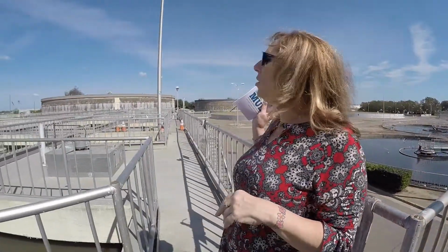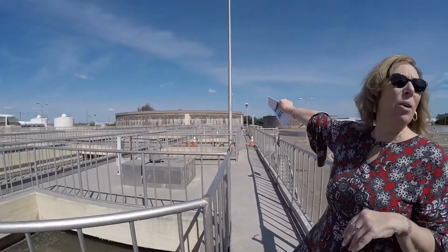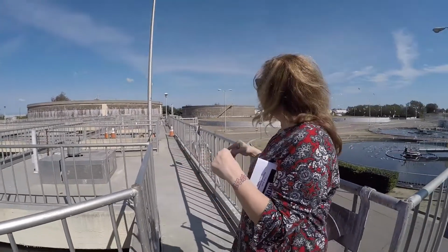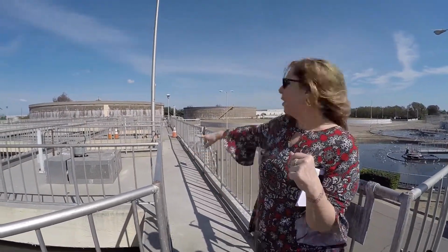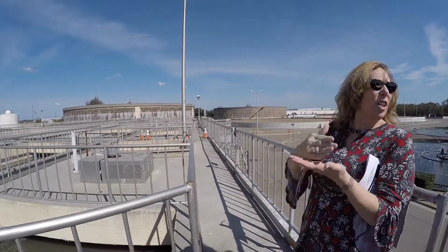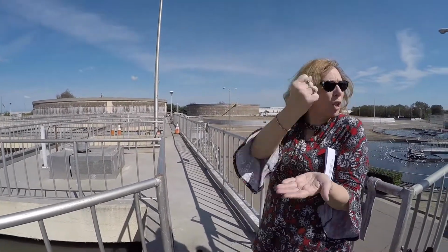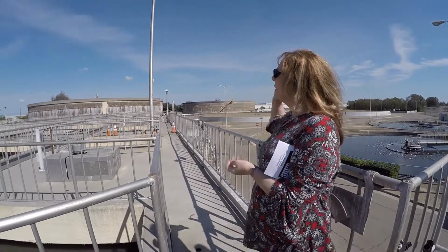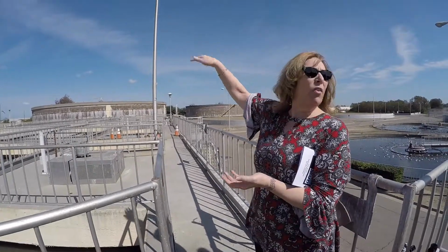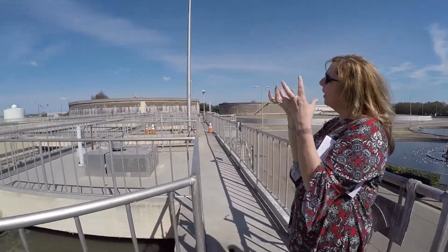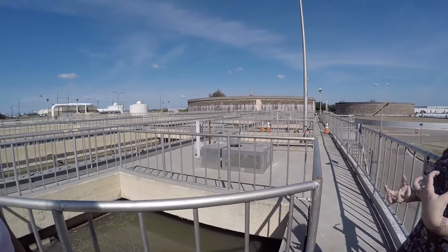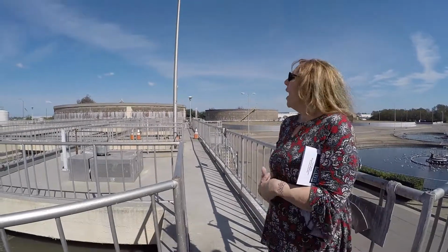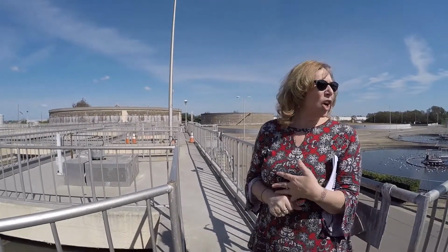Clear water goes to the secondaries, but it also goes over here to the biotowers. And what a biotower is, if you look inside of the biotower, it's full of green material. It looks like the cases that you put your sodas in, but it's plastic. And what happens is they sprinkle it over the top like a sprinkler, and it trickles down through the filters, and there's a bacteria growth that grows on the filter medium, and that removes the nitrates, nitrites, and ammonias.